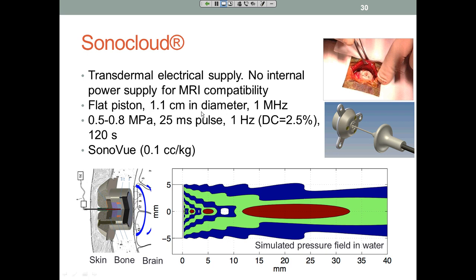The device is very simple. It's a flat piston, as you can see here, a centimeter in diameter, operating at 1 megahertz. The pressure range is between 0.5 and 0.8 megapascal, very similar to what others are doing with the extracorporeal device. Exposure duration is 2 minutes, and the PRF is 1 Hertz with a pulse length of 25 milliseconds. This is typically the pressure field that we can get, which is a simulated pressure field in water. What we hope to do is to open the blood-brain barrier very quickly on a quite large volume around the zone that was resected. Typically, the sonicated zone corresponds to the dimension of the transducer, which is a centimeter in diameter, and the depth depends on the attenuation.